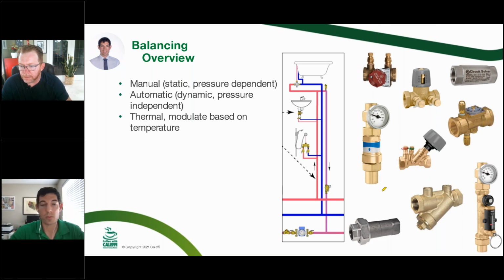That's a great way to go. People use those on a residential application on a recirc line with PEX or something like that to make sure you don't exceed that 2 feet per second. You just pick the cartridge and say, okay, this is the cartridge that I want, to make sure that we're not racing back through that recirc line. Would work for copper as well too.